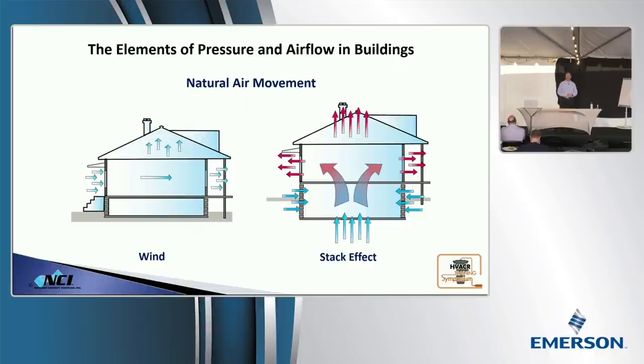Anybody having any oh crap moments yet? Because the air is doing what it naturally does. We can't assume it. You can have properly sized openings in a wall, and this will still happen. Isn't that interesting? Wind can cause this. It can also cause some goofy stuff to happen if you take the ducts vertical. If the wind is the only driving force that we have, if there's no wind, what happens to combustion air? No combustion air. You have to have an opening. You have to have a pressure difference across it.